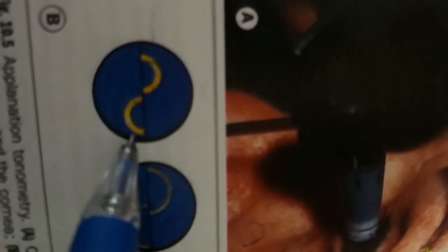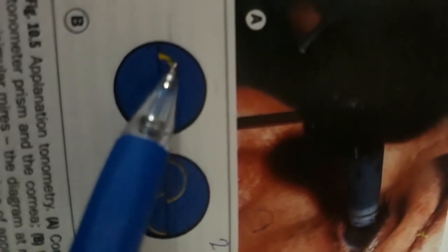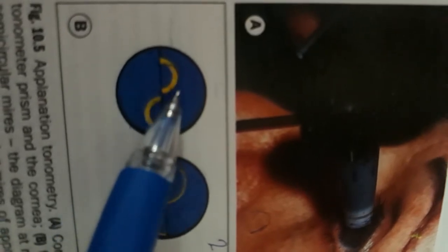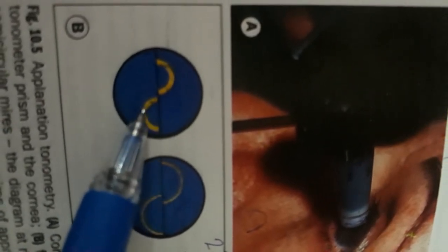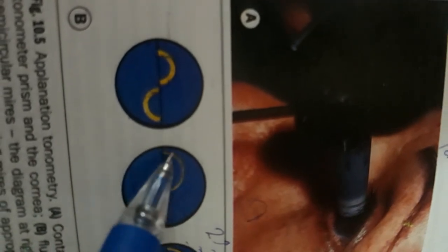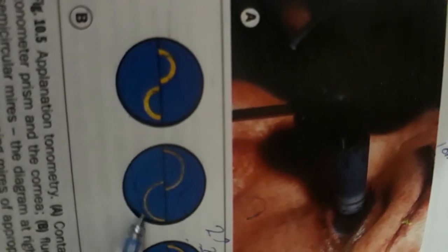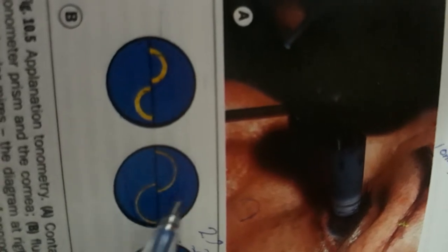A source of error is inappropriate fluorescein pattern. If fluorescein is excessive, it will result in mires being too thick. If fluorescein is insufficient, then the mires will be thin.